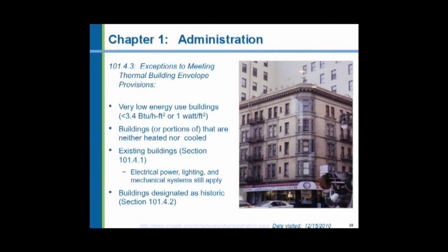Very low energy use buildings. Buildings that are not heated or cooled or heated only to 3.4 BTUs per hour per square foot need not comply with the code. Well, that's an odd number. Where did that come from? Well, that's the conversion between watts and BTUs. That means 1 watt per square foot.